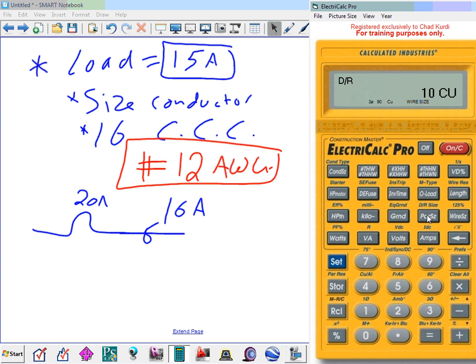I lost just 1 fixture, versus adding 1 more fixture and all your conductors change to what? Number 12 and number 10. And guess what? You can't add another fixture to it, by the way, because if you add another fixture, it becomes 17 amps, and you're limited to what? 16 amps, no matter what. And it wouldn't fit in the conduit either. Yeah. When we say 10 now, we're assuming you're going to get a bigger conduit. Any questions about this? Everybody can see the importance of that? I always like to throw this example.